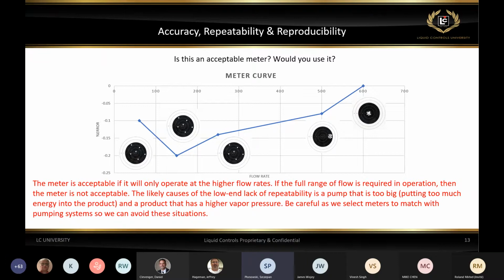So is there anything wrong with this meter? No. Is the system as a whole acceptable? Not. Because if you start running this meter at the lower flow rate, you will have accuracy, or again repeatability, issues. So it is really important when you're designing a system to make sure that all the components of the system match each other. So you're not generating too much pressure or too much energy on the pump, with that energy having no place to go, and then creating an issue on the meter side.